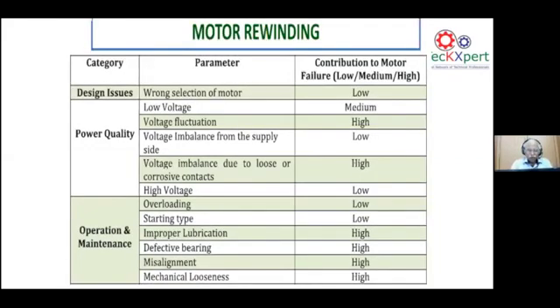So if we look at the motor rewinding that is happening in the industry now, the main contribution, let us go for the failure rate. What is the failure rate on low, medium, high? Just look at the high side: the voltage fluctuation or the voltage imbalance happening due to loose or corroded contacts is high, that is more in the industry. And on the operation and maintenance side, there is improper lubrication, defective bearings, misalignment, or even some places where the belt is given an over tension that breaks the motor shaft or the machine shaft. So alignment is also a cause in many industries of lost productivity or increased power consumption of the motor. The mechanical looseness or the mechanical tightness, the motor and machine should be optimally gripped. This is where we are losing.